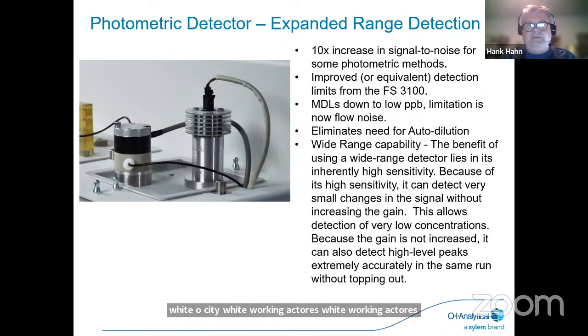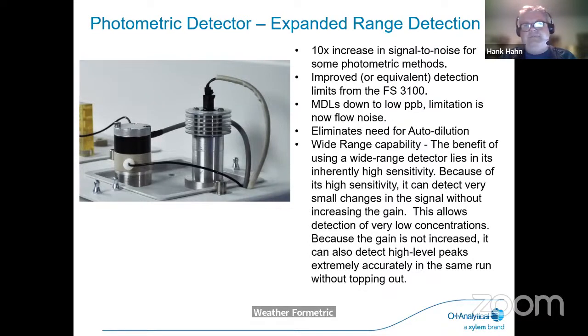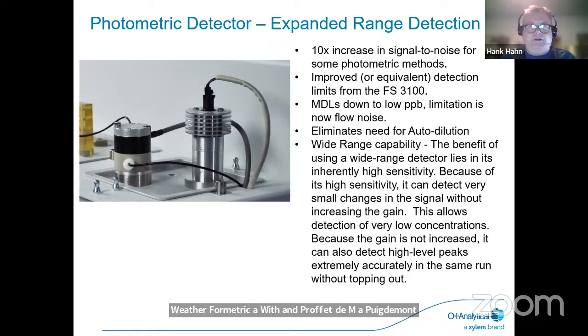With our photometric detector, it was known previously as a 550 detector. Also, with the expanded range detection, we have a 10x increase in signal to noise for some of the methods, also allowing you to do low levels like the low level phosphorus. We've improved the detection limits from the FS3100 with this detector. The MDLs are down to low parts per billion, and the limitation is now the flow noise. At this point, it does eliminate the need for auto dilution because we do have 4 orders of magnitude with the wide range capability of this. We do offer a diluter, the RML 600, and I have a little bit of information on that in the presentation.